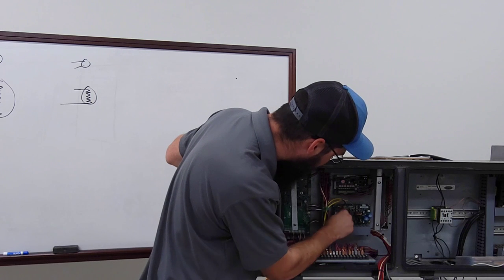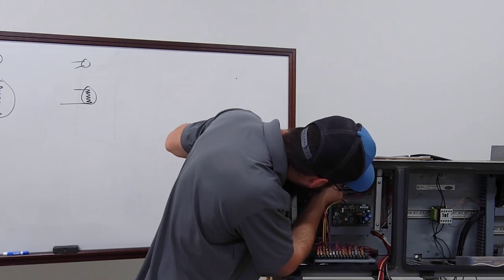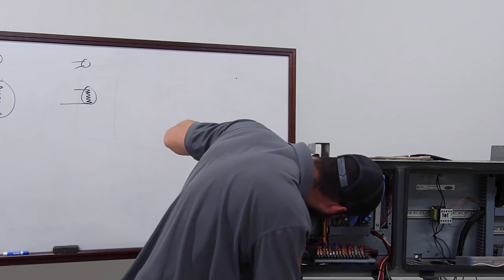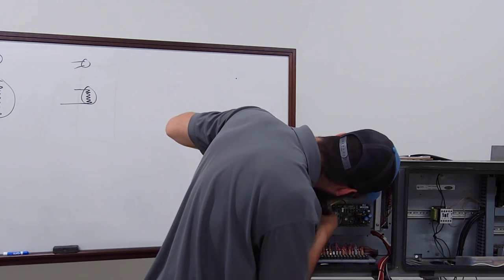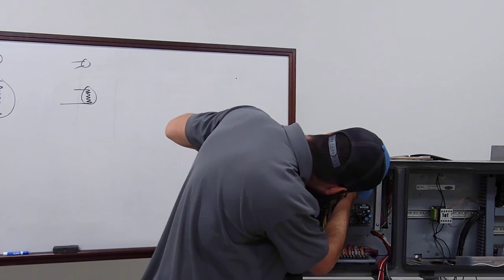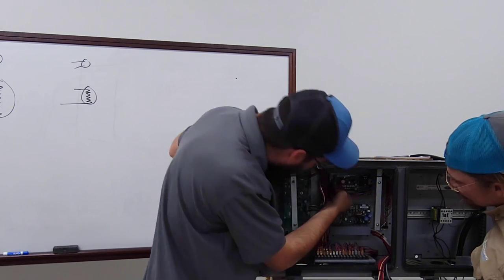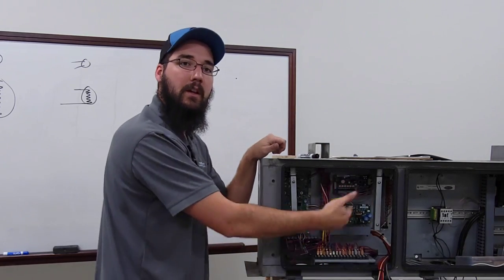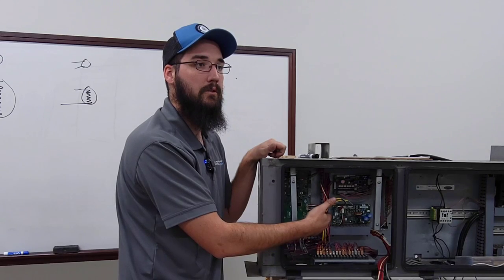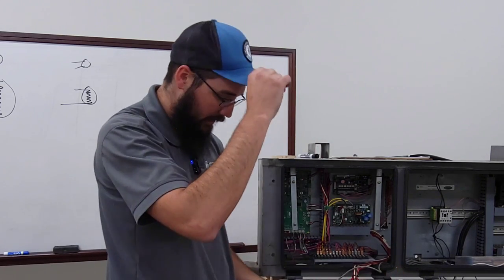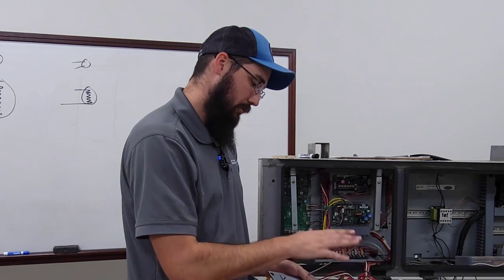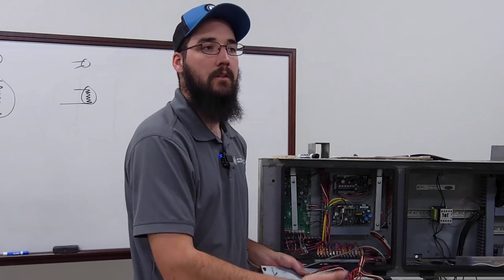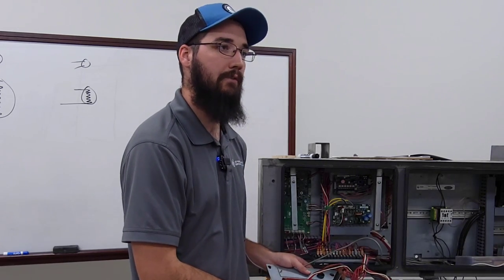Something else to point out: the vast majority of the time, these displays are just strictly a display. They do not control, house, or have any kind of parameters in them. So when they fail, it's just a chunk of plastic — nothing else to worry about. It's literally plug and play. If you do have a Navigator for a Carrier unit, this is where that Navigator would plug in — specifically you're going to use the LEN, L-E-N, network connection for that Navigator. Those navigators are extremely handy tools, and one Navigator module will work across the board with any Comfort Link communication system. You can take one off a chiller and go over to an RTU, plug it in, and you'll get the same function and operation.